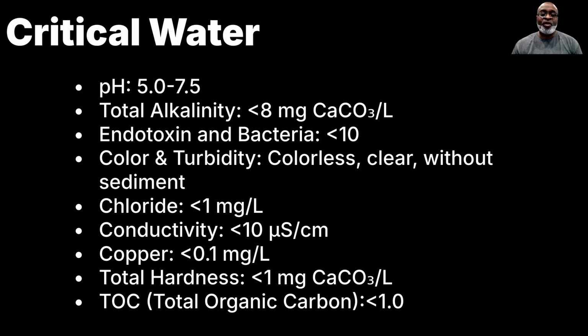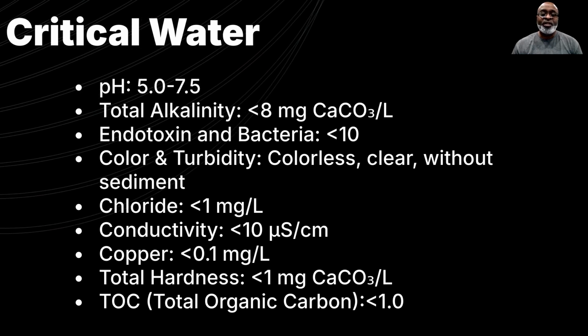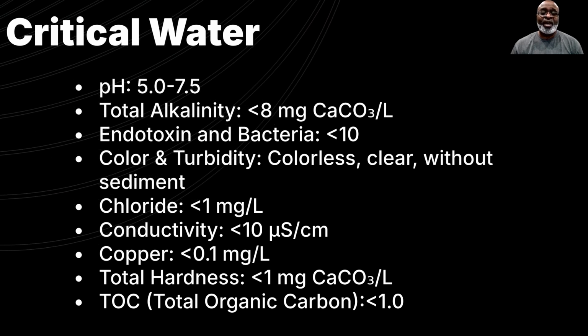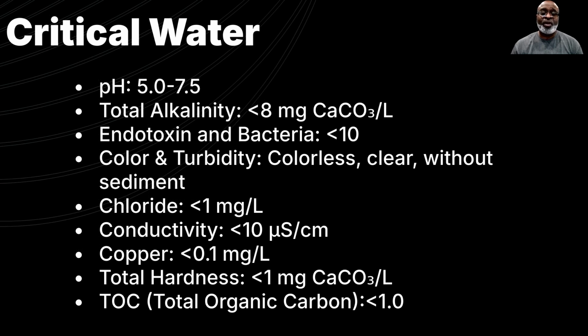Critical water is defined as water that has undergone extensive purification to remove impurities that could compromise sterilization processes. It is used in the final stages of medical device reprocessing, where the highest level of water quality is required to ensure compliance with ST108. Critical water must meet the following limits: pH 5.0 to 7.5, total alkalinity, less than 8 milligrams per liter of calcium carbonate to minimize residue formation. Bacteria and endotoxin, less than 10 to ensure microbial safety. Color and turbidity must be colorless, clear, and free of sediment to avoid visible impurities. Chloride, less than 1 milligram per liter to prevent equipment corrosion and contamination. Conductivity, limited to less than 10 microsiemens per centimeter, ensuring minimal ionic content. Copper, restricted to less than 0.1 milligrams per liter to avoid metallic contamination. Total hardness, less than 1 milligram per liter of calcium carbonate to reduce scaling and residue. Total organic carbon, TOC, should be less than 1. These stringent parameters ensure that critical water provides a pure and effective medium for sterilization, fully compliant with ST108.